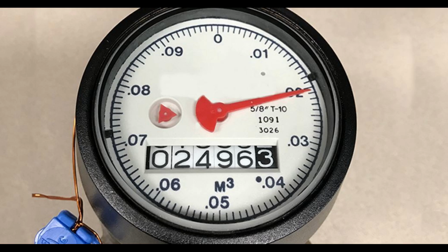Problems associated with metering arise particularly in the case of intermittent supply, which is common in many developing countries. Sudden changes in pressure can damage meters to the extent that many meters in cities in developing countries are not functional. Also, some types of meters become less accurate as they age, and under-registering consumption leads to lower revenues if defective meters are not regularly replaced. Many types of meters also register airflows, which can lead to over-registration of consumption, especially in systems with intermittent supply, when water supply is re-established and the incoming water pushes air through the meters.